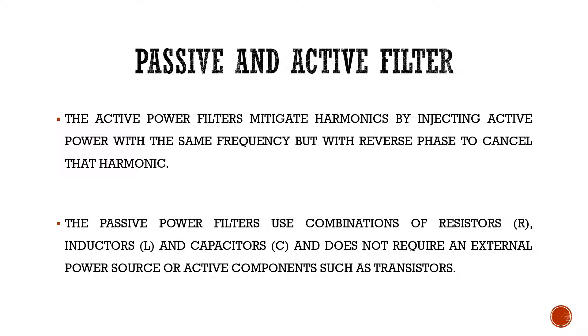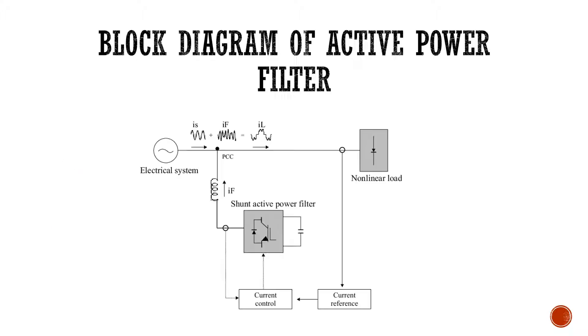Most commonly, active filters are used nowadays for harmonic compensation. This is the general block diagram of the active power filter. We can see here a generating system — that is the electrical system — which generates the power given to the system or the grid. The major source of harmonics in the system is the non-linear load, which causes harmonics in the grid. We need to compensate the harmonics caused by the non-linear load. For this purpose, we are getting the current reference from the load side.